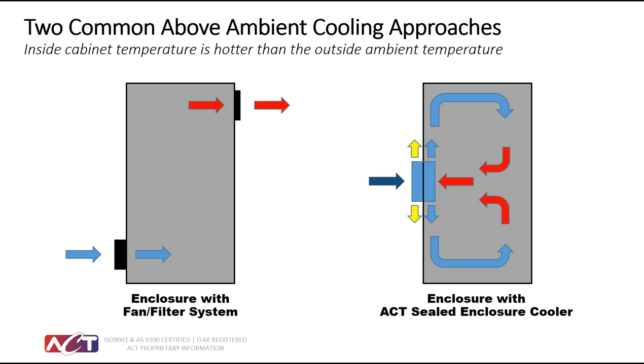So what we're talking about with ACT and our sealed enclosure coolers is that you would place a device, cut one hole, and then you're going to circulate the air on the inside and then reject the heat to the outside with our heat transfer methods that we'll discuss in a couple of slides coming up. So again, one hole cut and no air is exchanged between the outside of the cabinet and the inside of the cabinet. But yet you get ample circulation through the fans that are on the heat exchanger systems or the thermoelectric systems.